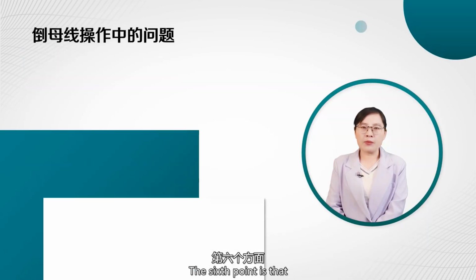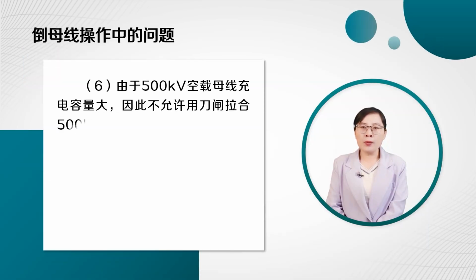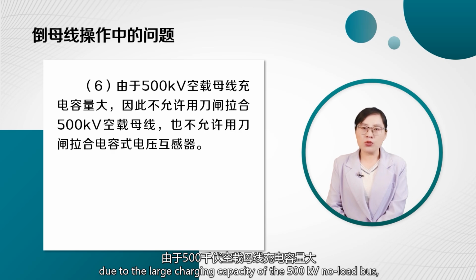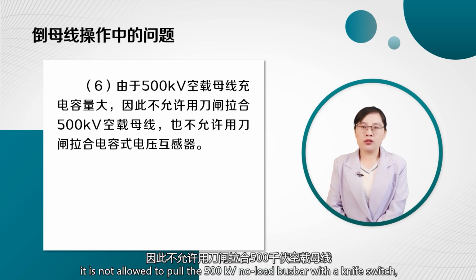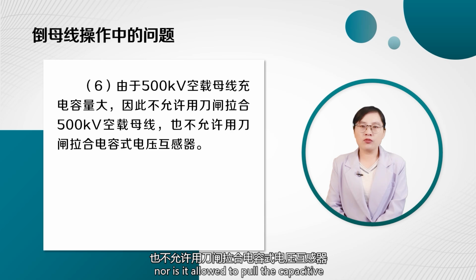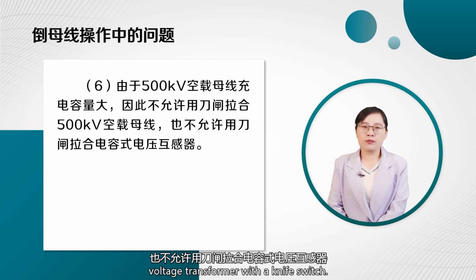The sixth point is that due to the large charging capacity of the 500 kV no-load bus, it's not allowed to pull the 500 kV no-load busbar with a knife switch, nor is it allowed to pull the voltage transformer with a knife switch.